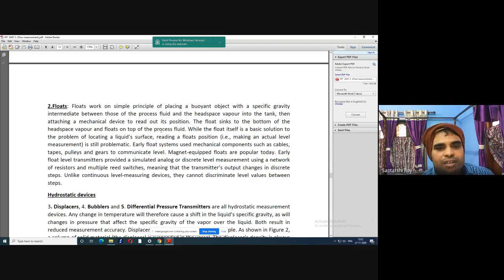The float sinks to the bottom of the headspace vapor and floats on the top of the process fluid. While the float itself is a basic solution to the problem of locating a liquid surface, reading a float's position, that is making an actual level measurement, is still problematic.